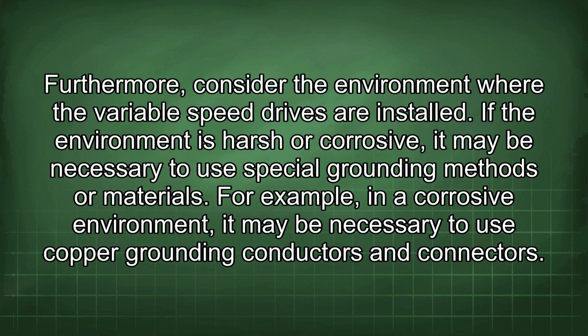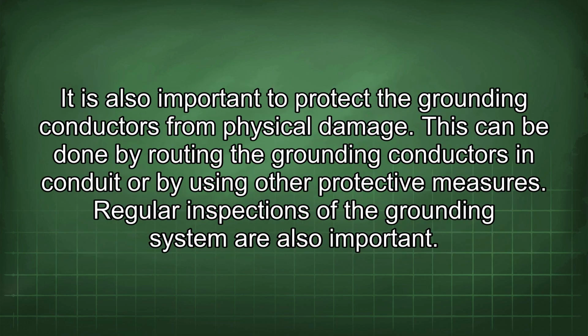Furthermore, consider the environment where the variable speed drives are installed. If the environment is harsh or corrosive, it may be necessary to use special grounding methods or materials. For example, in a corrosive environment, it may be necessary to use copper grounding conductors and connectors. It is also important to protect the grounding conductors from physical damage. This can be done by routing the grounding conductors in conduit or by using other protective measures.